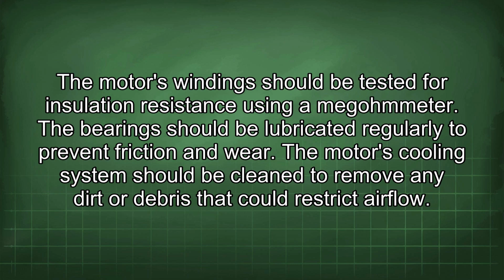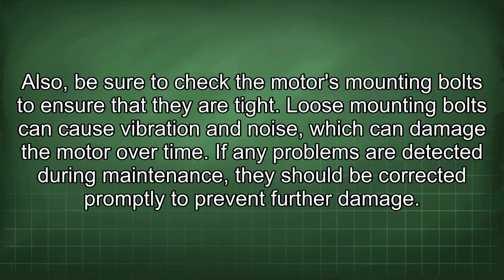The motor's cooling system should be cleaned to remove any dirt or debris that could restrict airflow. Also, be sure to check the motor's mounting bolts to ensure that they are tight. Loose mounting bolts can cause vibration and noise, which can damage the motor over time. If any problems are detected during maintenance, they should be corrected promptly to prevent further damage.